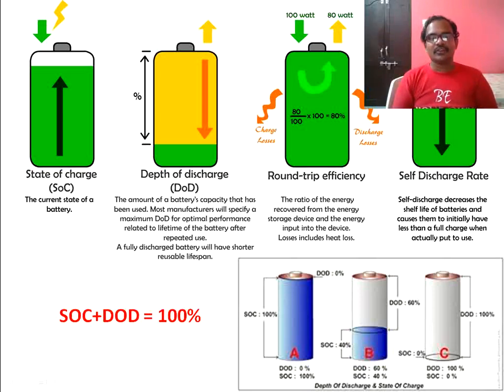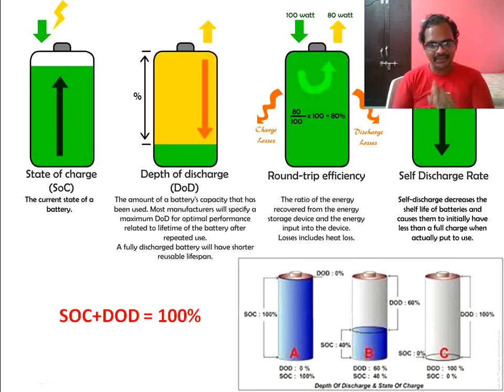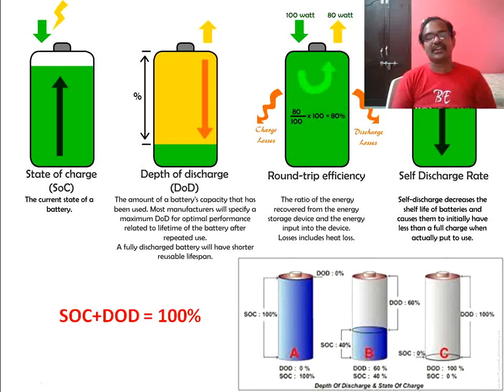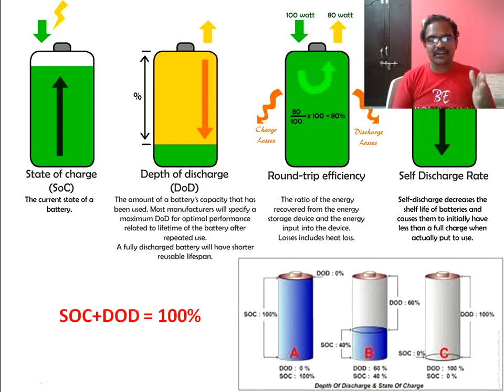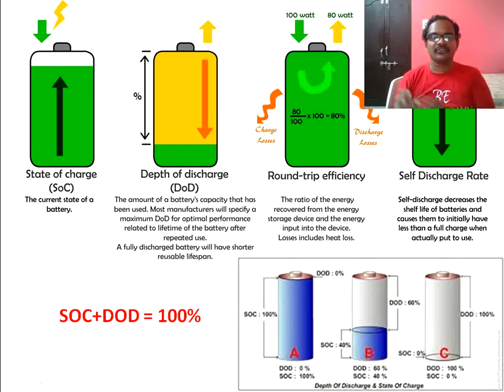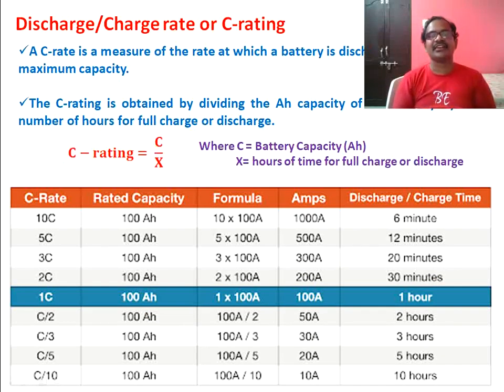An important thumb rule: state of charge plus depth of discharge always equals 100%. Case A — if the state of charge is 100%, the depth of discharge is 0%. Case B — if the battery is at 40% state of charge, the depth of discharge is 60%; SOC + DOD = 40 + 60 = 100%. If the battery is completely drained, the state of charge is 0% and the depth of discharge is 100%, giving 0 + 100 = 100%. So SOC + DOD always equals 100%.